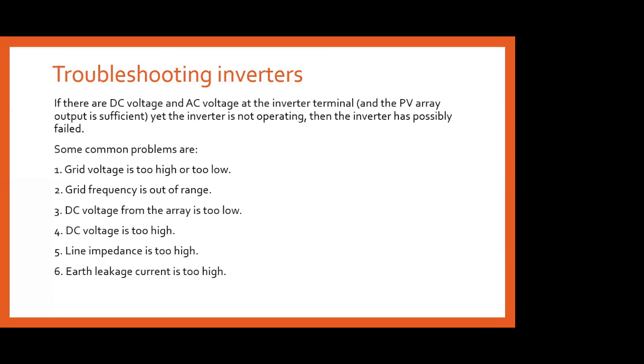The next one is if the line impedance is too high. If the line impedance is too high, then connections on the AC side should be checked. Is there any loose connection or something like that? If the problem continues, then it may have something to do with the grid, and once again we have to contact the electricity distributor itself.